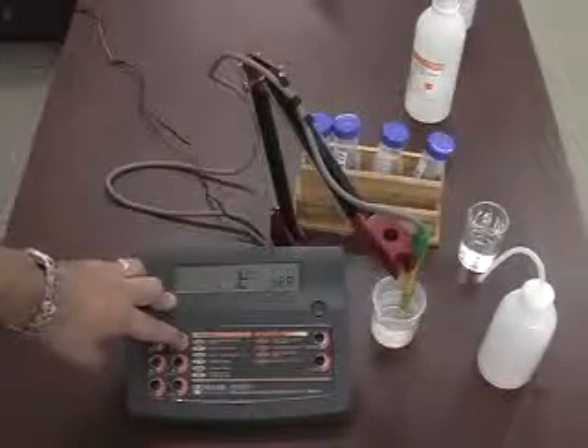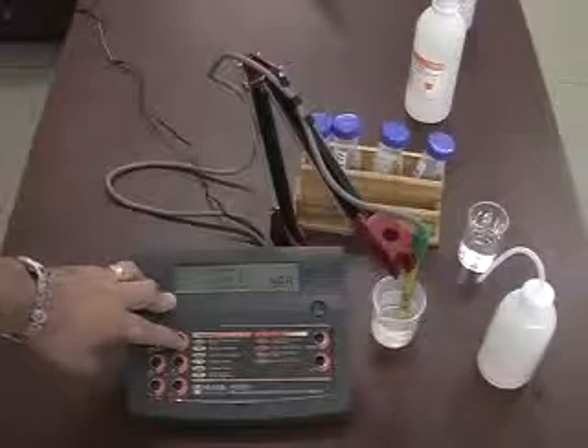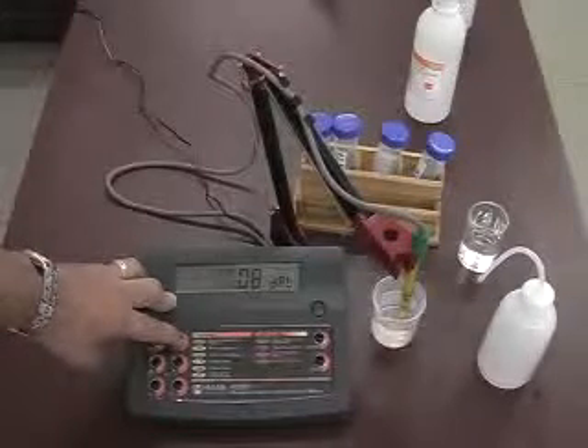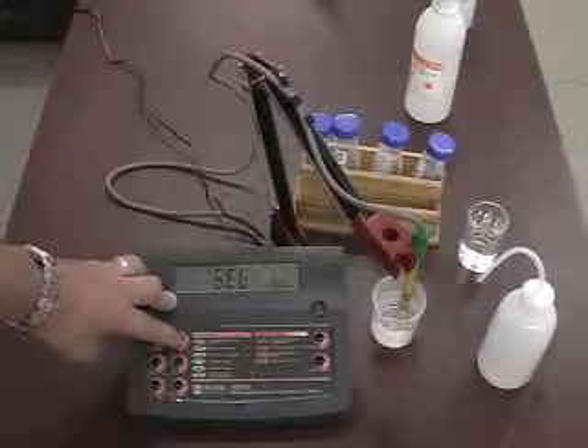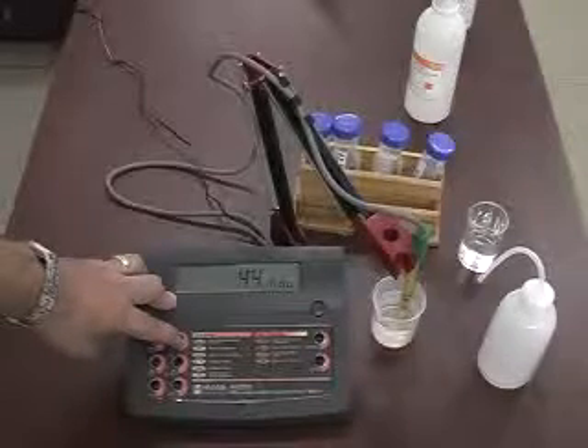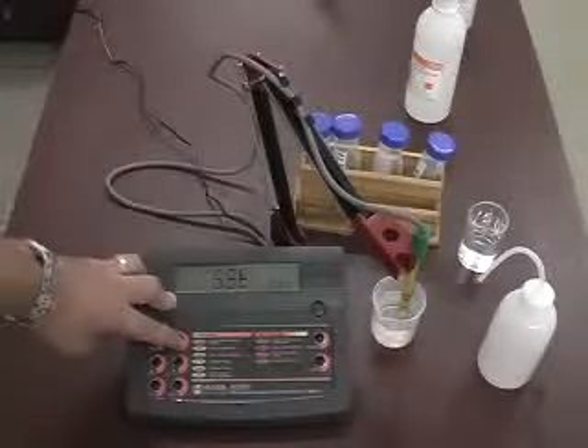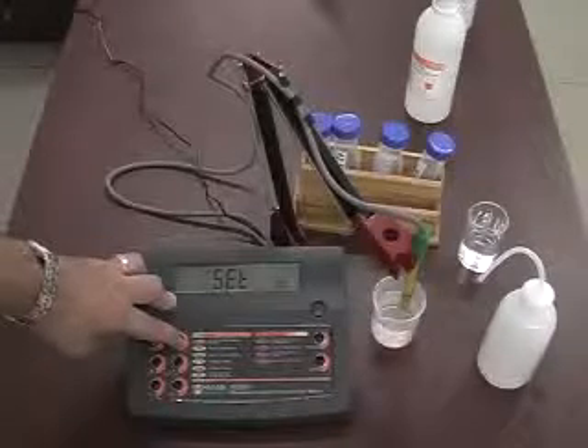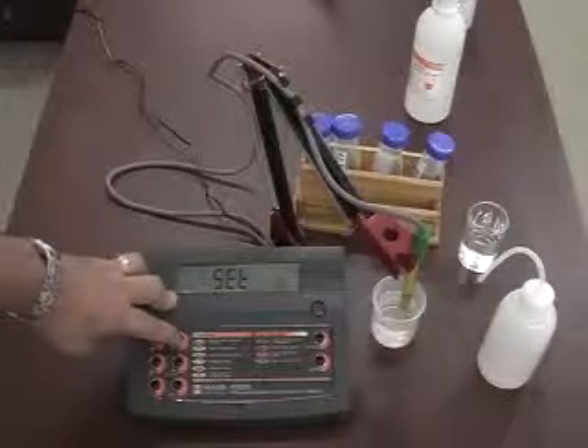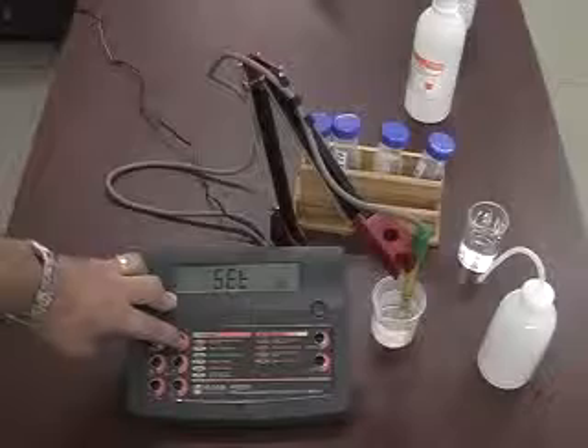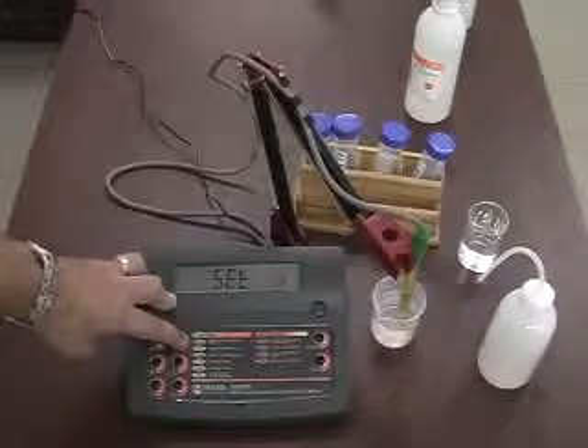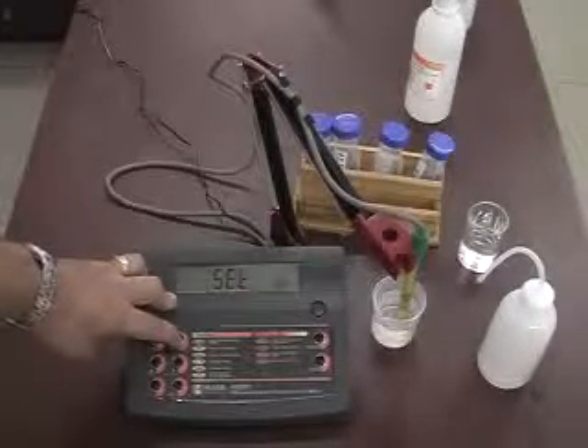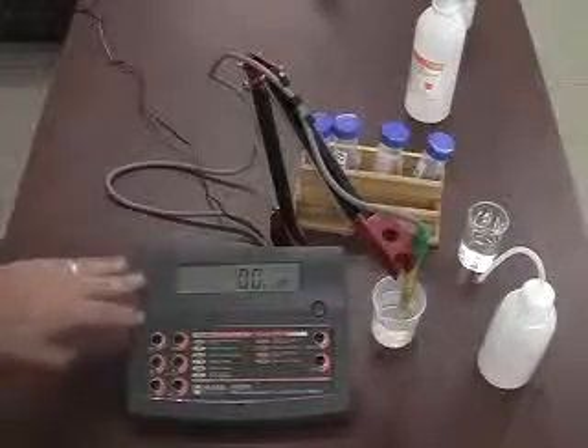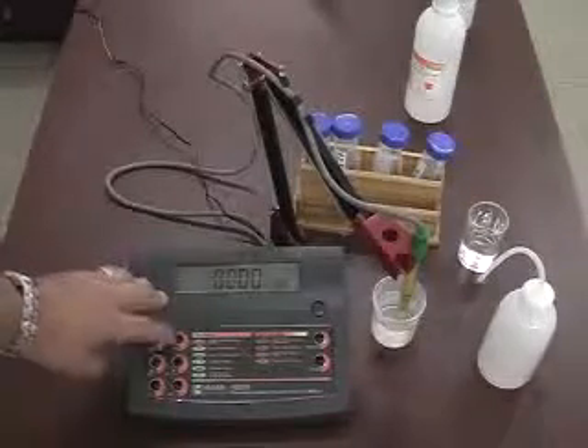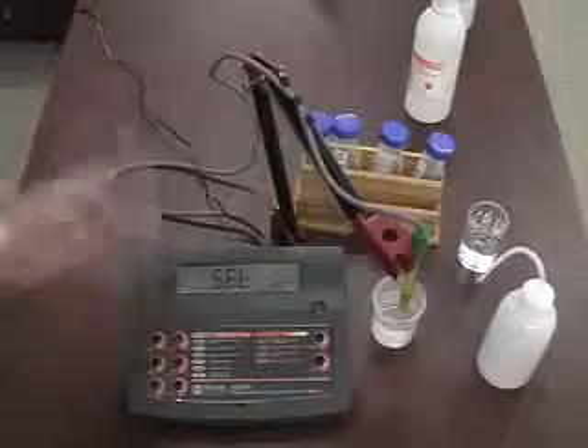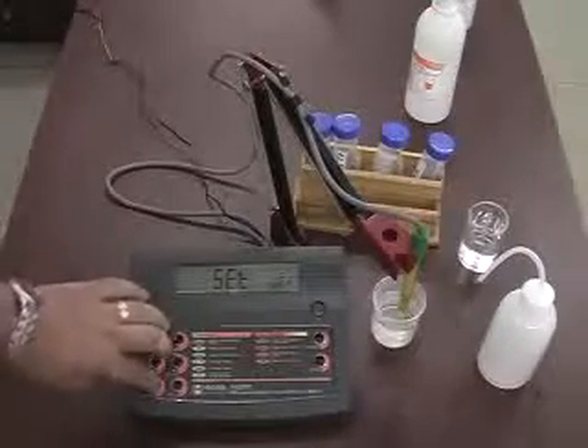The year is set for 2010, the date set for today, August 20th, and then the time set for 1:44. That's the time of the day right now. We have the instrument ID number. If we had multiple meters within a certain plant and we are using the logging function of the meter and transferring data into a computer, this would be used to identify one particular meter that you're taking this information from. After that, that's pretty much the setup options that we have available.